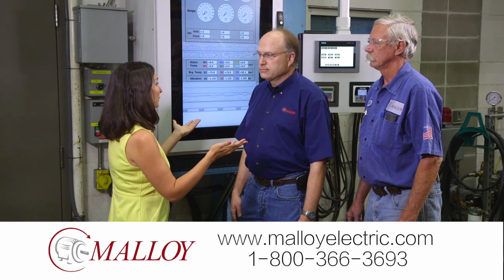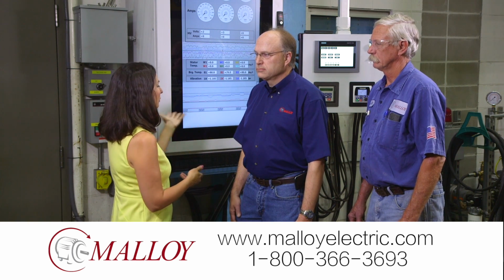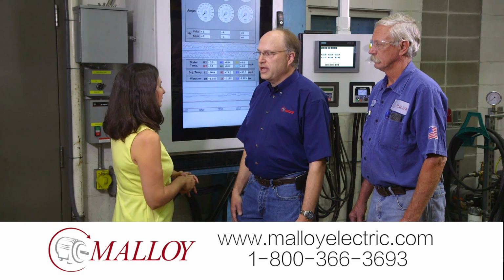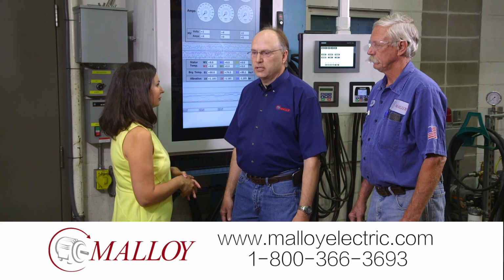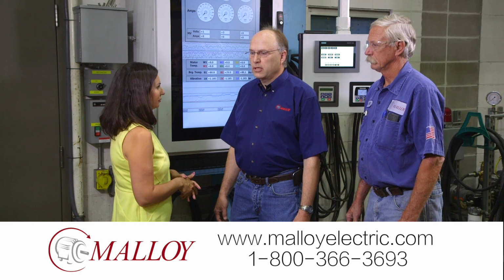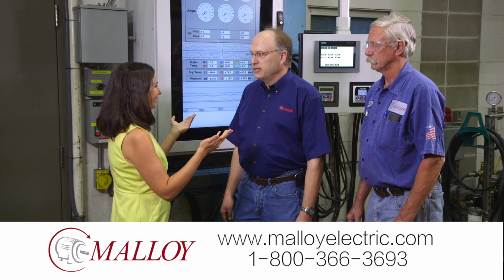So let's say it goes well. It's time to send it back to the customer. What kind of data are you then able to share with them? We can share a lot of the load data, the temperatures of the bearing systems, the winding systems, the voltage applied, the current that it's drawing no load, those types of parameters. And they get it all in a digital file? They can, yes. That's pretty cool.